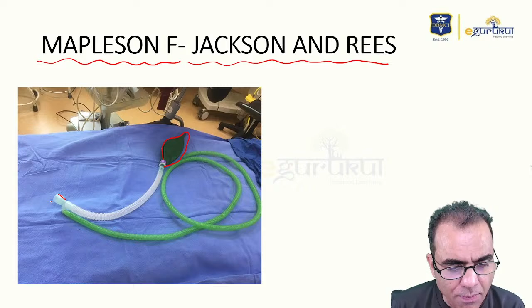It was made complete by attaching a breathing bag to it, by the scientists Jackson and Rees, which is also called Mapleson F. You can see they just attached a breathing bag to this Mapleson E, which is just a T-piece to which the tube was attached. Until here, it is Mapleson E. Once the bag was attached, it becomes Jackson and Rees. So Jackson Rees, or Mapleson F, is simply a modification of Ayre's T-piece, which was an incomplete circuit. Now, fresh gas flow recommendations for Jackson Rees.